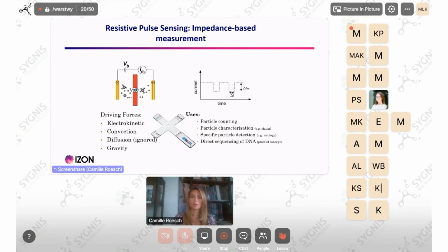So depending on how clean your sample is and how well you take care of your nanopores, you can prolong the lifetime quite a lot. That's entirely up to the users. But as a minimum, you can do up to 10 samples per nanopore. And then the software helps you know if the nanopore has been overused already, if it's too dirty, or if you can still use it.